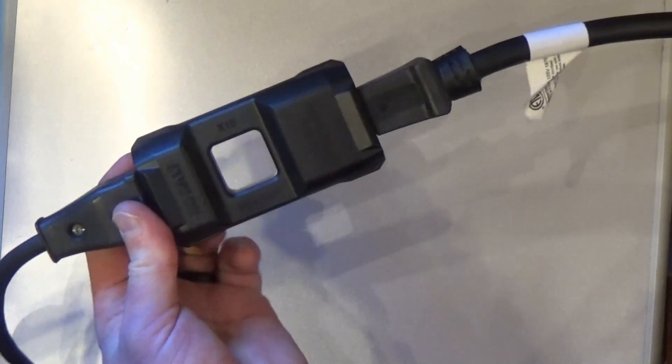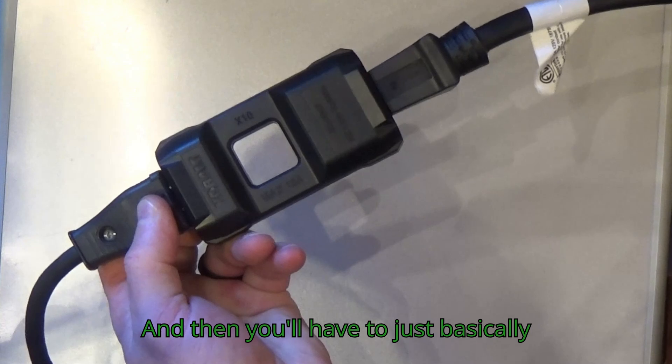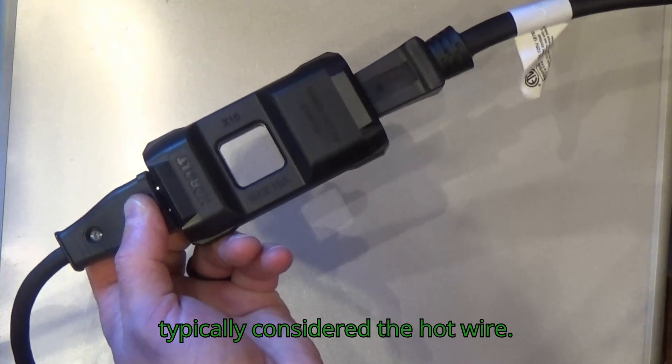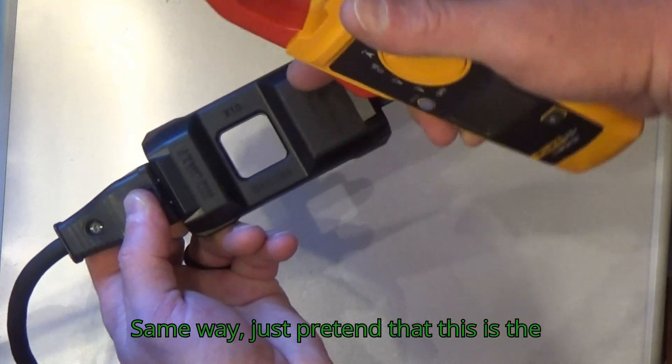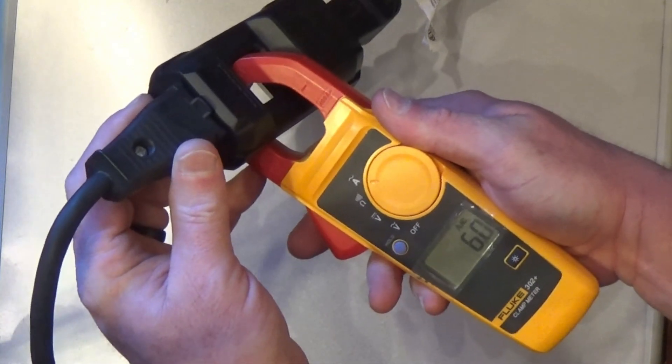Now to do this in the real world without this adapter for 120 volt AC, you have to have the cable pulled apart. And then you'll just basically catch around the black wire, which is typically considered the hot wire. Same way, just pretend that this is the white neutral wire and this is the black hot wire. Just clamp around it while it's in amp mode.